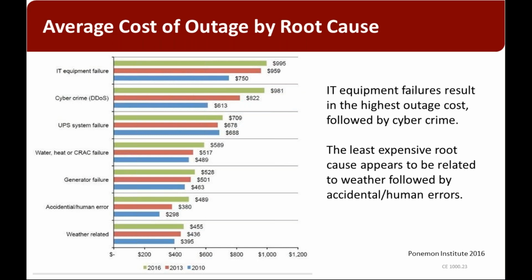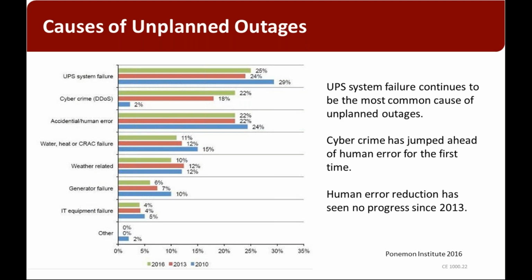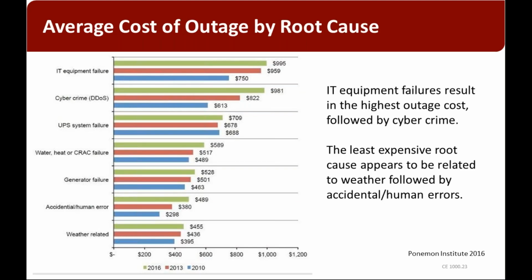Then the average cost, in addition, let's just go back and I'll make one more comment on that UPS. This does not mean your UPS is flawed. This does not mean it's unreliable. In most cases, it means you have not done the proper maintenance and understood or done the investment over time or done the training. So it isn't the engineering side of putting in a UPS and sizing it. It's how it is operated and maintained, or not operated and maintained.